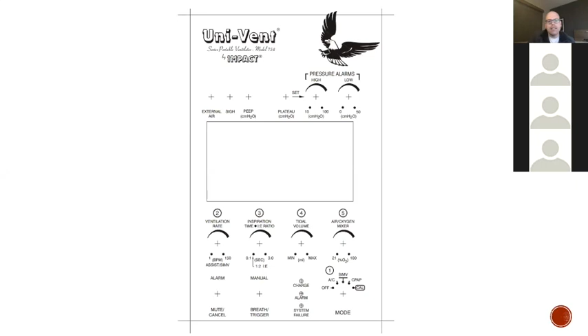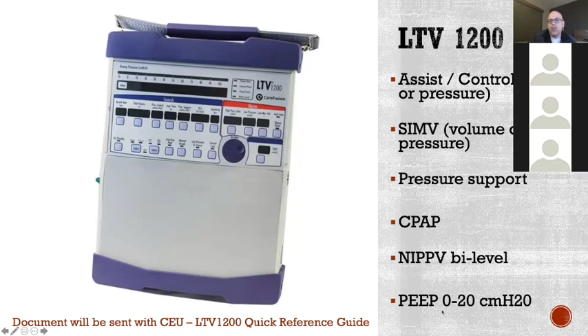The last one in the strategic stockpile is the LTV 1200. This one is more of a multimodality ICU type ventilator. It's arguably going to be the most sophisticated of the three in the stockpile, and it can do assist control with volume or pressure. So this one can do pressure modes of ventilation. It can do SIMV with volume or pressure. It can do pressure support, so we can do SIMV with pressure support, so that patient doesn't feel air hungry. It can do CPAP, it can do NIPPV, or BiPAP, and it can do PEEP, 0 to 20 of PEEP.